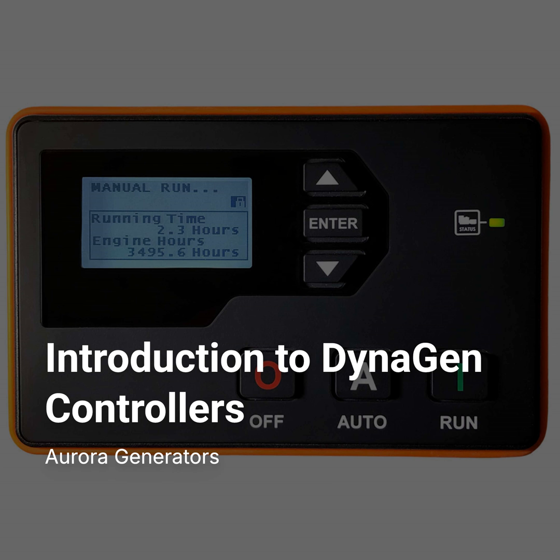There's also a long time run feature, where you set a duration for the engine to run after a trigger, like a manual start. And finally, a maintenance timer, which counts down the time and triggers alerts when the next scheduled maintenance interval is getting close. So from the immediate start sequence right through to long-term maintenance scheduling, there's lots of time-based control.